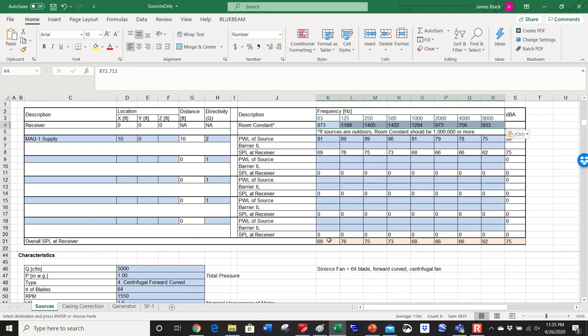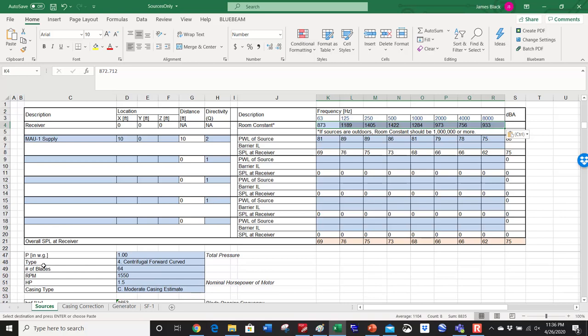But here's the ASHRAE 87 calculation, with all the variables you need to put in. Q in this case is the air capacity, the volume of air being supplied, so 5,000 cubic feet per minute. Volumetric airflow is what this is. And then the total pressure in inches of water, so 1 inch. That's basically the pressure the fan sees through the system of ductwork, the pressure drop it's pushing against.